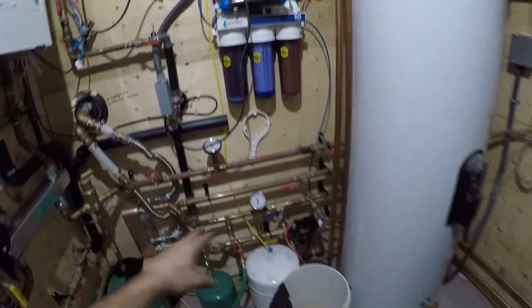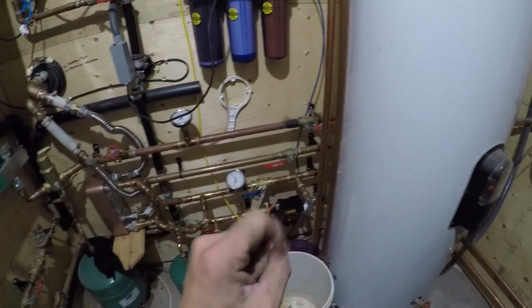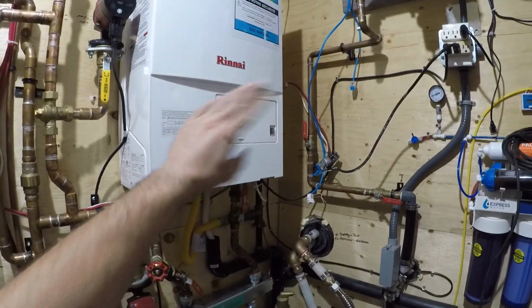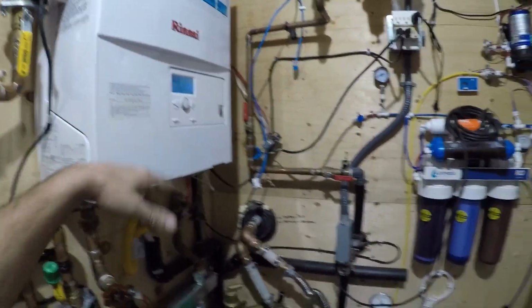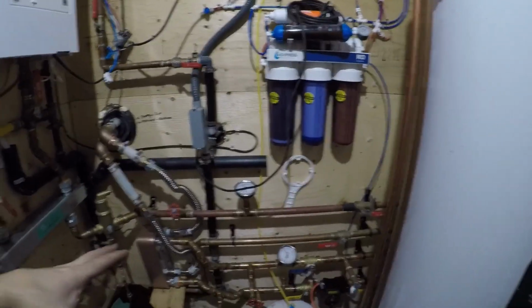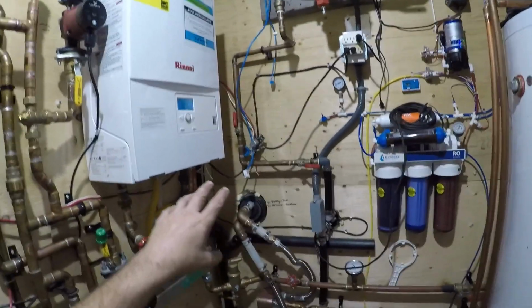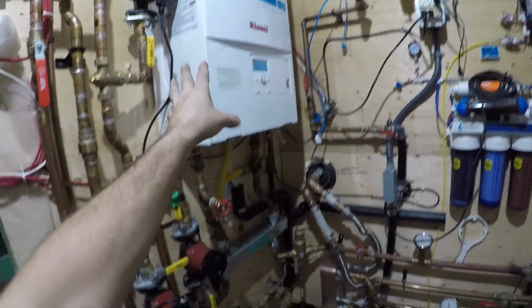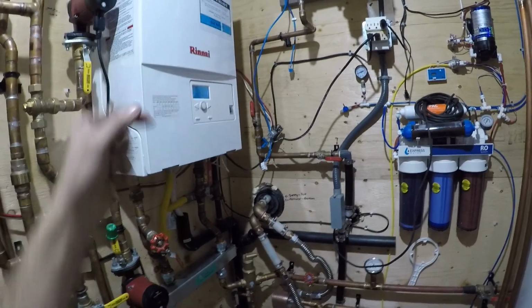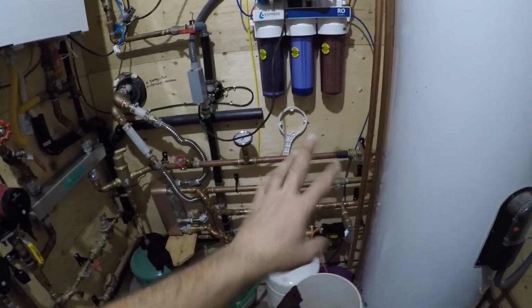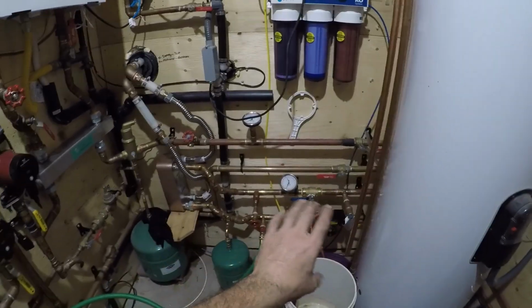So what's going to happen is when the home automation system sees that it's 150 degrees coming in, it's going to disable the start on the gas boiler. So the gas boiler won't turn on once there's temperatures of 150 degrees going into this buffer tank. Technically, the automation should disable this boiler pretty much all winter. But I'm going to leave it hooked up, so if we go away and temperatures drop below about 150, then the boiler can fire up.